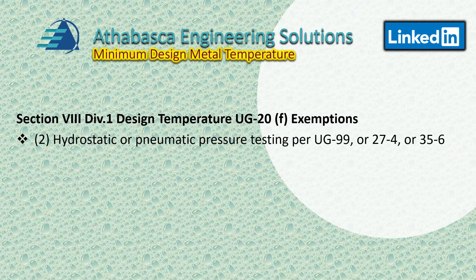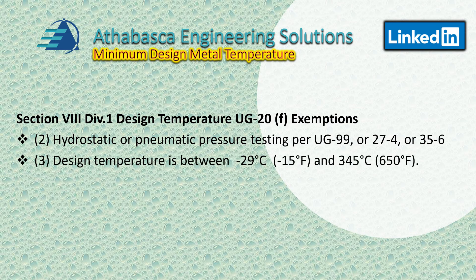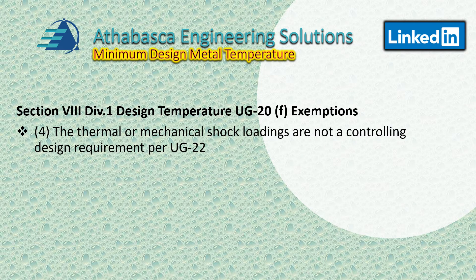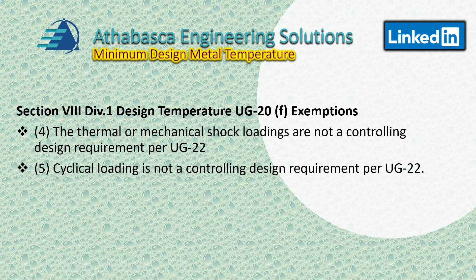The second condition is it must be hydrostatically or pneumatically pressure tested per UG99, or mandatory/non-mandatory appendices 27-4 and 35-6 found at the back of the code. Third, design temperature must be between minus 29 and 345 degrees centigrade. Fourth, thermal or mechanical shock loadings are not a controlling design requirement per UG22. Fifth, cyclic loading is not a controlling design requirement per UG22. If you meet all five criteria, the design qualifies for an exemption.